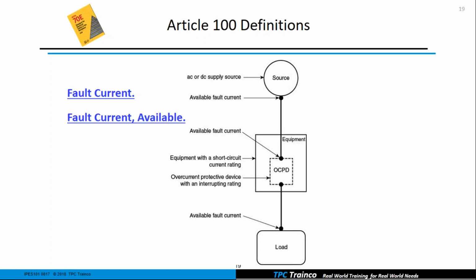It also gives us an idea about short circuit current rating for our equipment, to make sure that it is rated higher than the available fault current. It talks a little bit about interrupting rating, so that our overcurrent device can have a higher interrupting rating than the available fault current. So very nice that they put this in, and they've done a lot in this document with fault current. So very good that they gave us a nice diagram here.